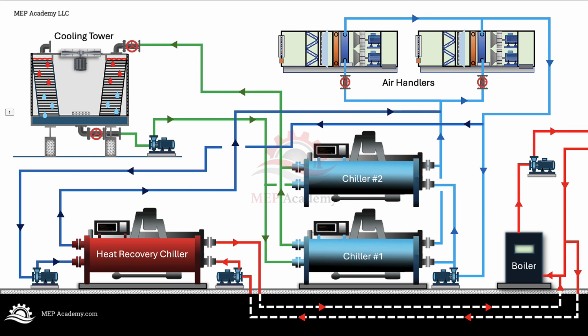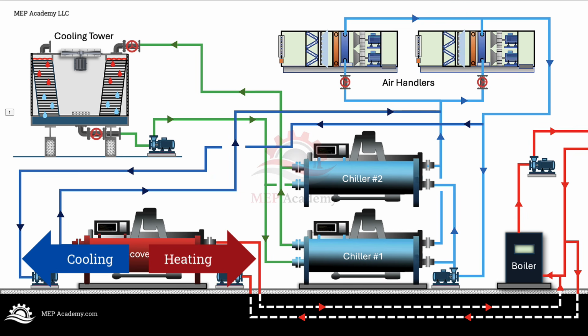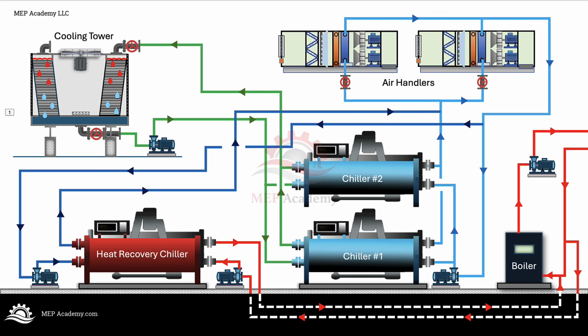The chiller is doing two useful jobs at the same time. It is cooling one load and heating another load. This is why heat recovery chillers are often compared to water-to-water heat pumps. They move heat from a lower temperature water loop to a higher temperature water loop. The cooling load becomes the source of heat. The heating load becomes the place where that heat is used.